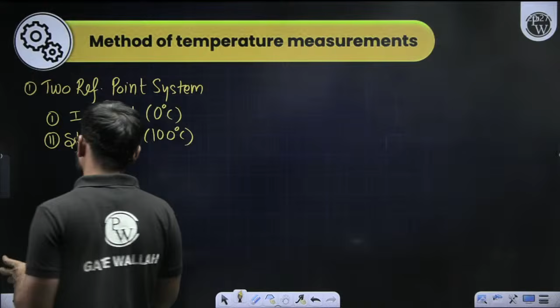Means T is equal to A plus B into P. T is the temperature, A and B are constants, and P is a thermometric property depending upon your system. Let's say it is a constant pressure gas thermometer, then P is volume. If it is a thermistor, then P is electrical resistance. If it is a mercury glass tube thermometer, then P is length. Now if I write this equation at the ice point, then this value will become 0, A plus B into P ice.